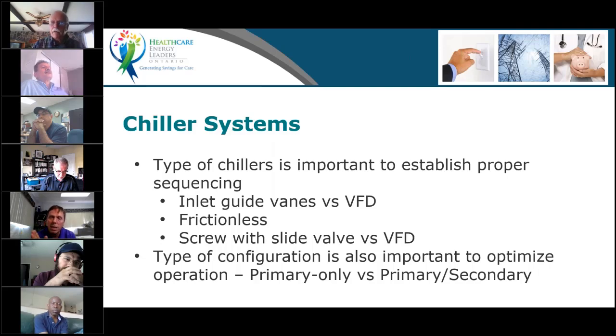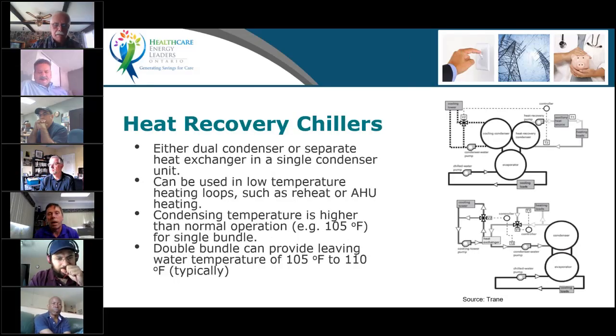If you're in luck, you have a secondary loop with a central bypass. You're in luck in the sense that this is not a very efficient system, because you're bypassing centrally when your load is low. But the good news is this can be converted at a fairly low cost to variable flow, because you don't have to change a bunch of three-way valves at every one of your coils. You can only change the setting on the bypass, close that bypass, install a VFD, and convert the system to variable flow. There can sometimes be more complexities. I'm simplifying here, but that is a measure that I've seen implemented, and I have implemented in a number of buildings.